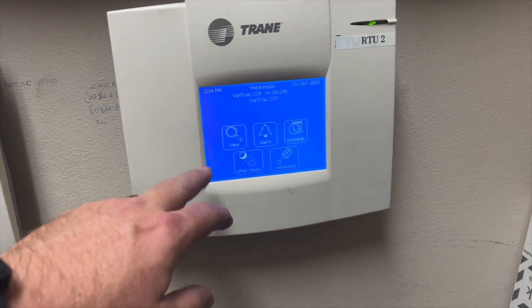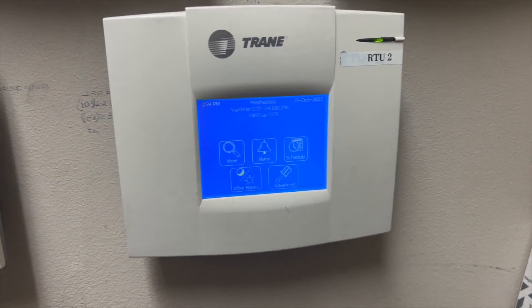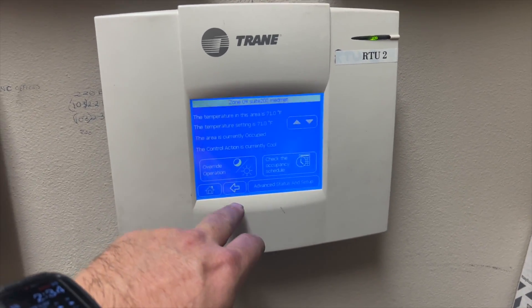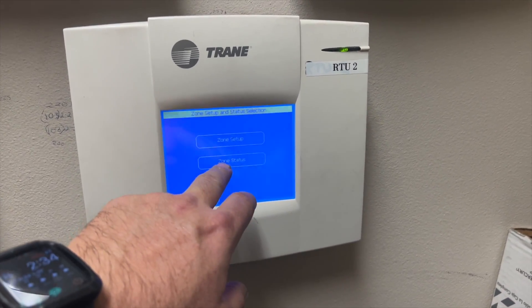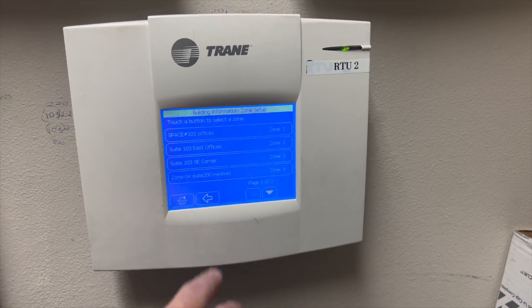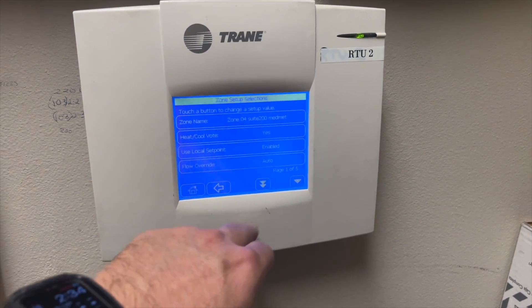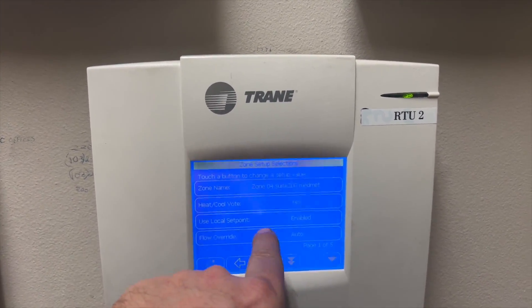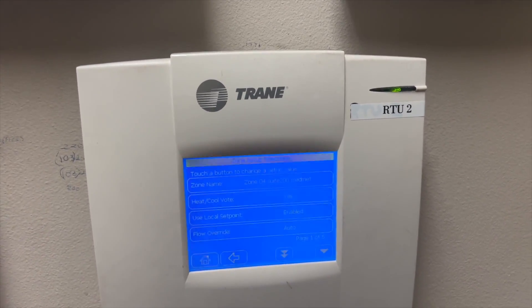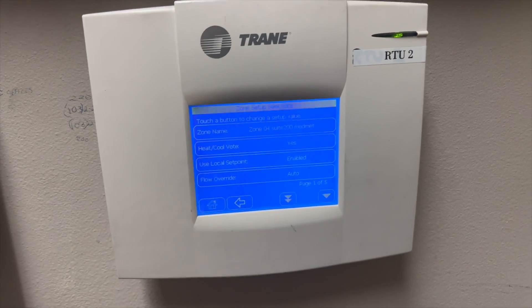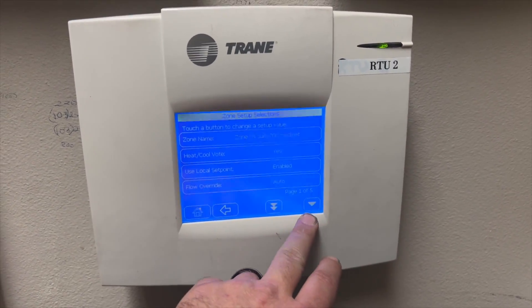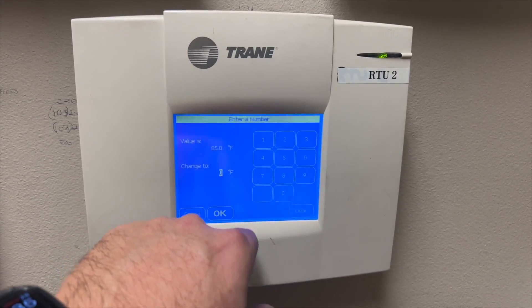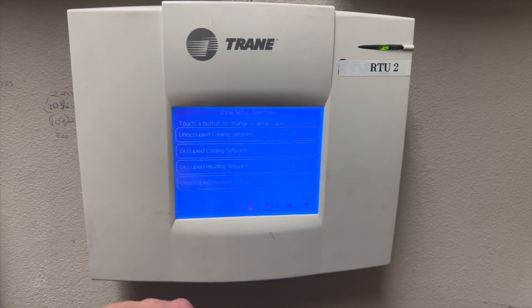You go into View, access your zone, go into Advanced, then Zone Setup. Choose your zone and you can make changes — you can even rename it, turn heat/cool on or off, and use local setpoints. You can disable their thermostat dial so they can't control it. This also shows you your unoccupied setting where you can make changes.